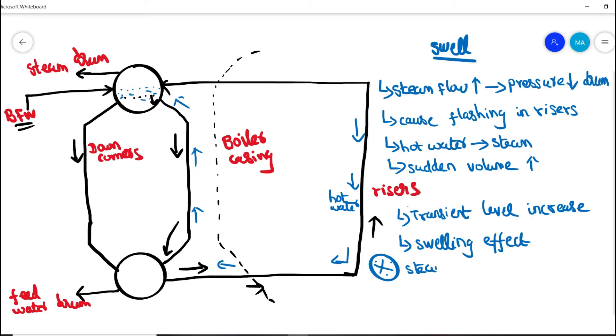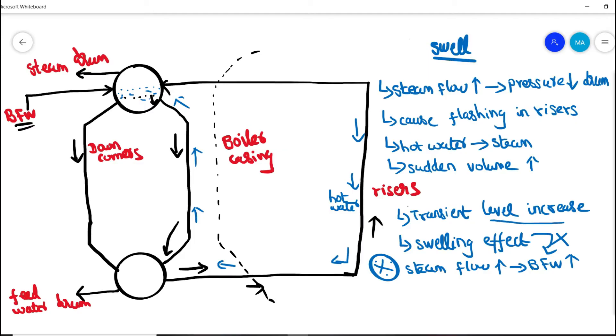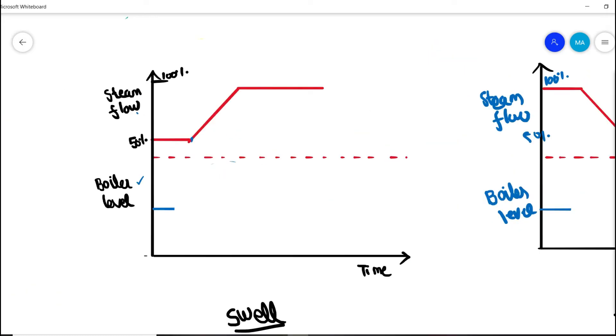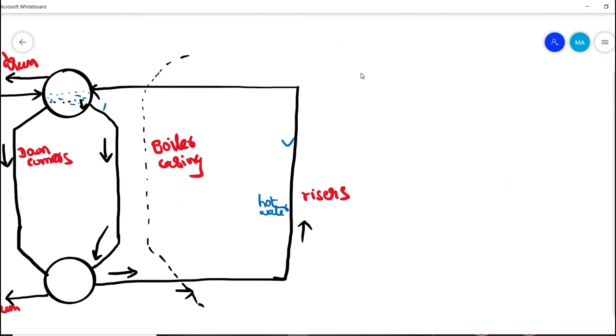Normally, when steam flow increases, the boiler feed water flow should increase so that more steam is generated. But due to the swelling effect, it causes a transient high level, and the boiler feed water would be reduced or cut instead. Looking at the graphical representation — the x-axis is time and the y-axis has two components: boiler level and steam flow. During idle condition, steam flow is at 50%, and when steam demand suddenly increases, the swelling effect occurs in the boiler level.